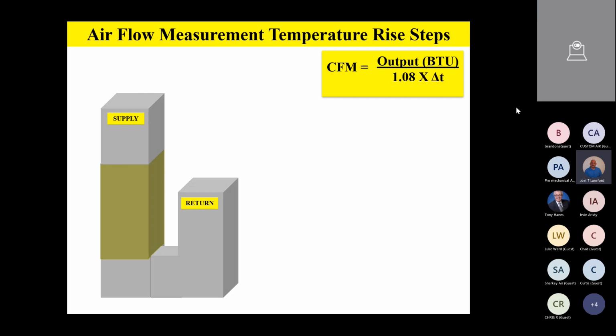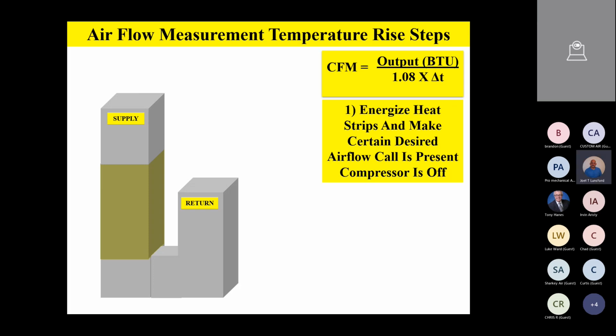Now that sounds like a mouthful, but let's talk about this formula a little bit. CFM is equal to the output of the device in BTUs divided by 1.08 times the delta T, or temperature difference between supply and return. When we apply this formula, like I said, it's very simple, and once you do it a few times, you'll see how simple it is. So number one, we're going to energize the heat strips on this air handler, and we're going to make certain that we're on the desired airflow call. In other words, we select whatever speed tap we're testing, and make sure the fan is blowing on that desired speed tap.